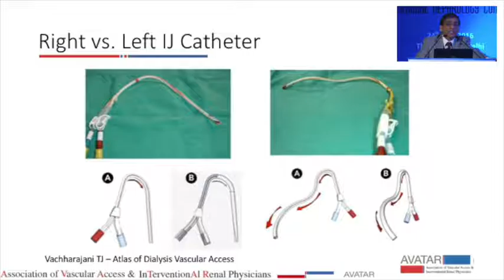And again, in clinical practice, very often the catheters do get connected in a reverse configuration, by which I mean the arterial lumen is used for venous return and the venous lumen is used for blood pull. So when the catheter is used in a reverse configuration, is that catheter good enough to provide adequate dialysis, meaning a blood flow of more than 300 and a recirculation rate of less than 10%?